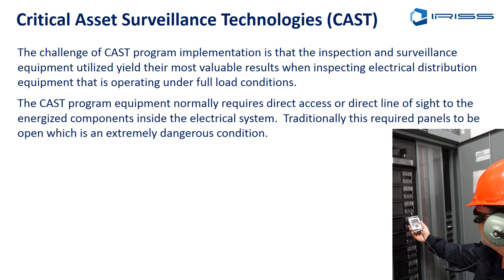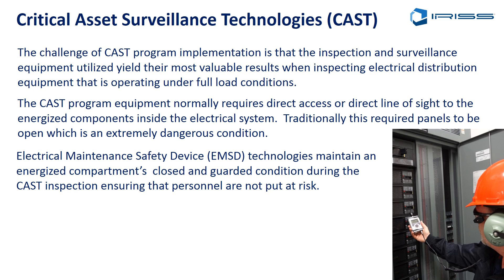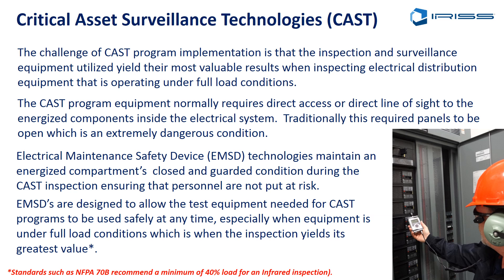Ultrasound allows us to listen around door seams or panels, but for a sealed system like a transformer cable box, it's very difficult to detect an airborne emission when you can't get inside the equipment. This is where we look at what we call Electrical Maintenance Safety Devices, or EMSDs. These technologies maintain an enclosed and guarded condition during a CAST inspection, ensuring that engineers and inspectors are not put at risk, while allowing the test equipment needed for CAST programs to be used safely at any time — especially when the equipment is under full load. With an infrared window or ultrasound port, I can get the data I need under full load conditions with the panel stays closed, which makes the inspection much more valuable.